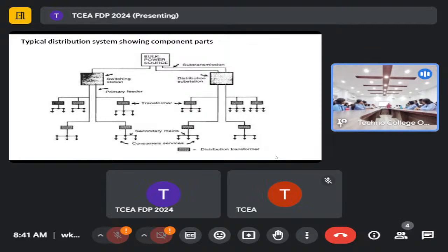Let me explain in a simple way. Suppose at the generation point the voltage is 11,000 volts, that is 11 kV. This voltage level is stepped up from 11 to 132 kV. That 132 kV travels to the city, then is stepped down from 132 to 11, or 132 by 33 kV. This 33 kV is distributed to different load centers, where there are substations. 33 kV is the primary distribution level. After it goes to those substations, it is stepped down again from 33 kV to 11 kV, so 11 kV is also primary distribution.